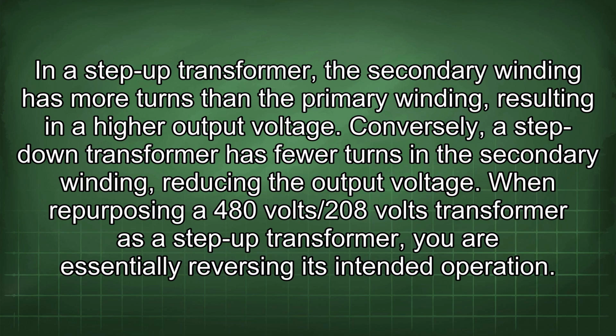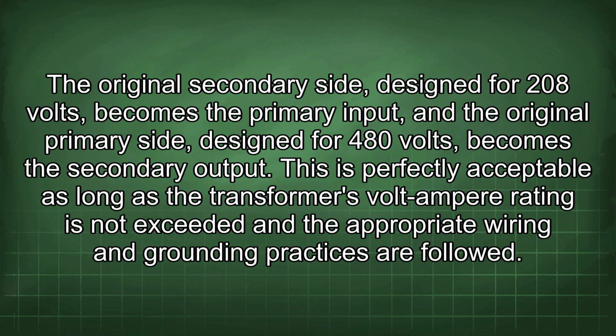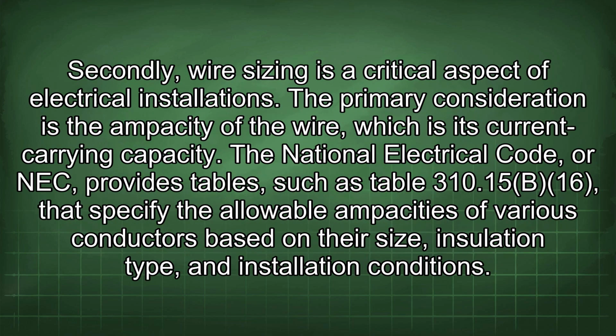When repurposing a 480 volts/208 volts transformer as a step-up transformer, you are essentially reversing its intended operation. The original secondary side, designed for 208 volts, becomes the primary input, and the original primary side, designed for 480 volts, becomes the secondary output. This is perfectly acceptable as long as the transformer's volt-ampere rating is not exceeded and the appropriate wiring and grounding practices are followed. Secondly, wire sizing is a critical aspect of electrical installations.